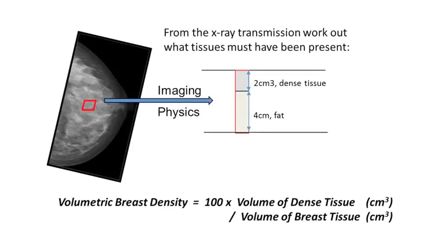We have to understand the physics and how the transmission depends on the various imaging parameters — kilovoltage, tube current, exposure time, and breast compression thickness, which is very important to know. With this information we can compute the transmission of radiation through the breast and from that estimate the volume of the breast itself, the volume of the dense tissue, and what we call volumetric breast density, which is just the ratio of those two quantities.